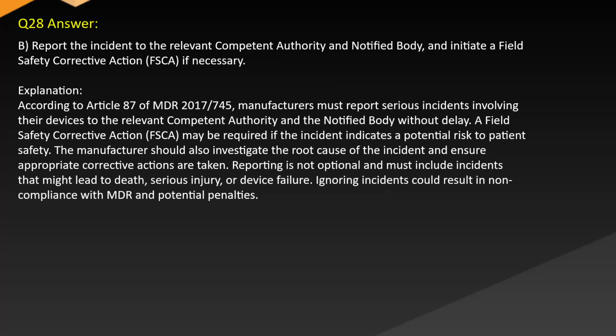Answer. B. Report the incident to the relevant competent authority and notified body and initiate a field safety corrective action (FSCA) if necessary. Explanation. According to Article 87 of MDR 2017-745, manufacturers must report serious incidents involving their devices to the relevant competent authority and the notified body without delay. A field safety corrective action (FSCA) is required if the incident indicates a potential risk to patient safety.